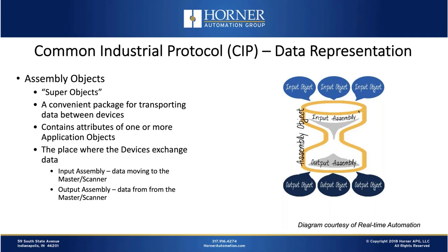Let's talk about a special type of object called assembly objects — these are really super objects. An assembly object is a convenient package for transporting data between devices. It contains multiple attributes from typically more than one application object, and it's really the place where devices exchange data. For instance, an assembly object will likely contain an input assembly with a collection of input objects, and an output assembly that's a collection of output objects. If an OCS is communicating with a third-party PLC over a CIP-based protocol, you're going to be exchanging data through assembly objects including input and output assemblies.